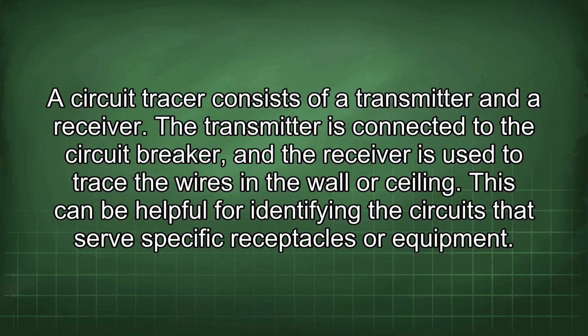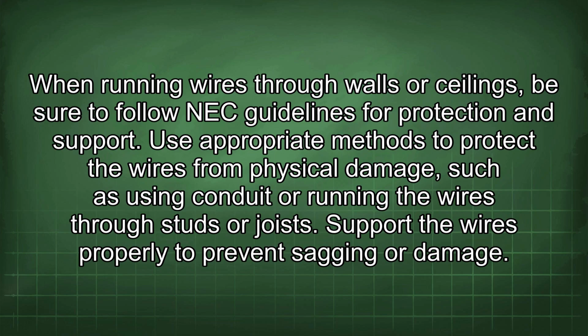A circuit tracer consists of a transmitter and a receiver. The transmitter is connected to the circuit breaker, and the receiver is used to trace the wires in the wall or ceiling. This can be helpful for identifying the circuits that serve specific receptacles or equipment. When running wires through walls or ceilings, be sure to follow NEC guidelines for protection and support. Use appropriate methods to protect the wires from physical damage, such as using conduit or running the wires through studs or joists.